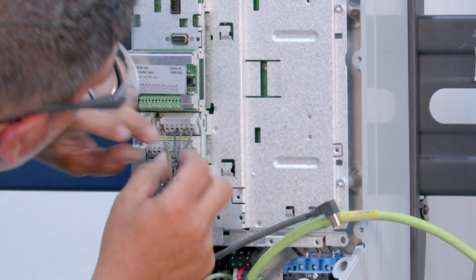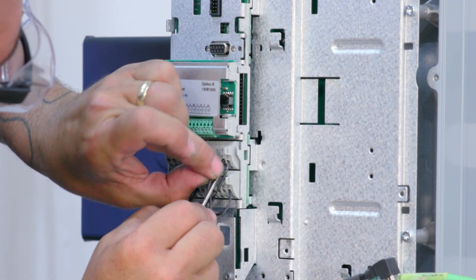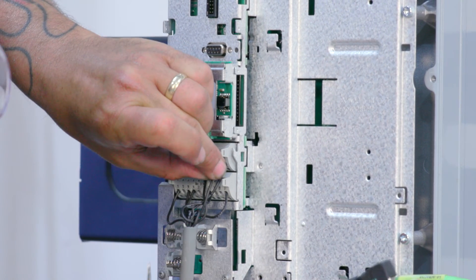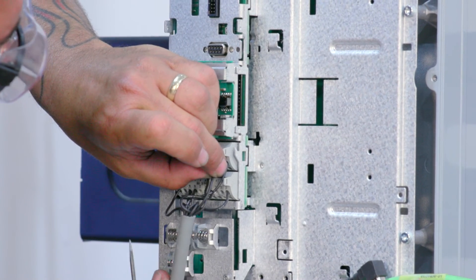Now we'll wire our thermal sensors. Take one wire from the PTC sensors to VFD terminal number 20, and the other wire from the PTC sensor to terminal 33 of the VFD.